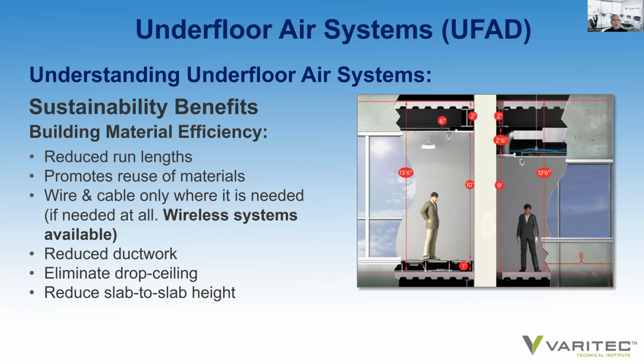So, sustainability benefits for UFAD systems. Reduced run lengths of ductwork. Consequently, you don't have a lot of galvanized sheet metal to be addressed at some time down the road from the building, certainly if it's to be remodeled. Promotes the reuse of materials. Wire and cable is minimal. In fact, wireless systems are available today. You don't even need to run cable underfloor to service variable air volume floor diffusers or linear or perimeter linear troughs. Reduced ductwork, drop ceilings can be eliminated, reduce slab to slab floor heights in a building. A lot of material savings need to be addressed before UFAD is assessed as a mechanical comparison to conventional HVAC.